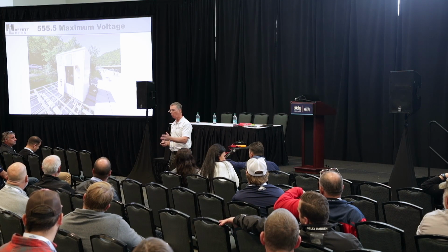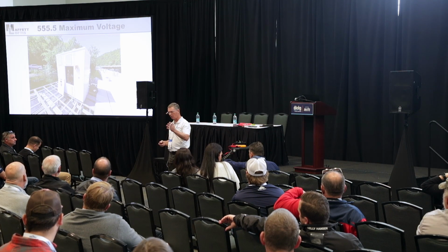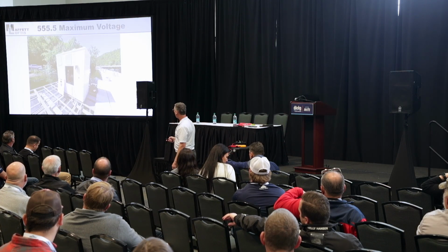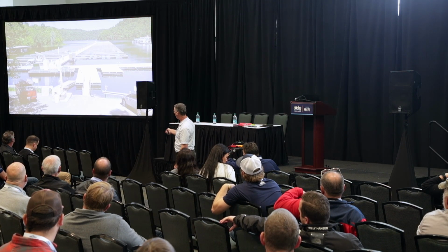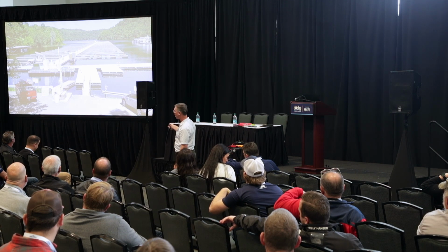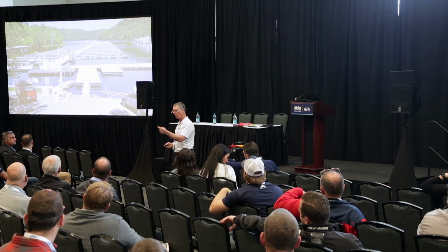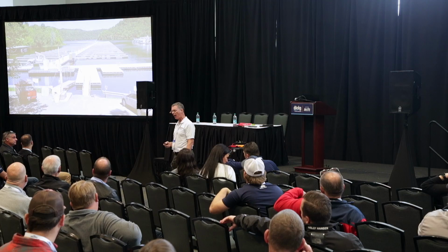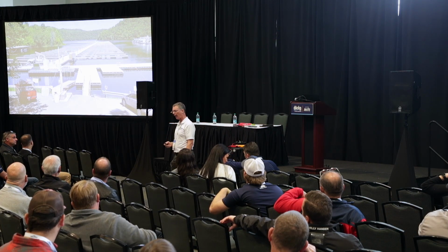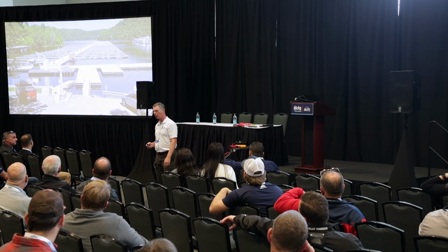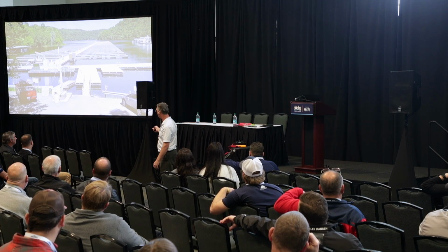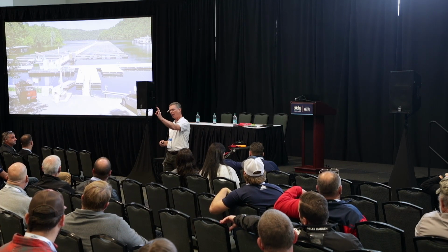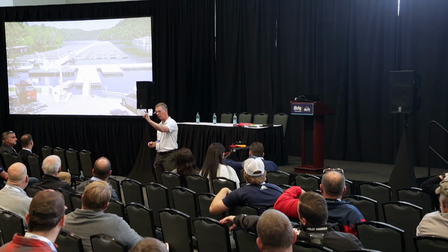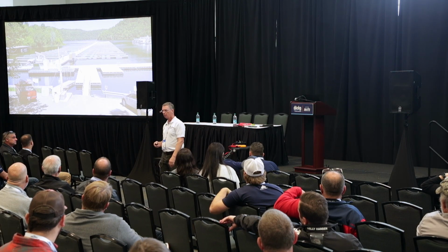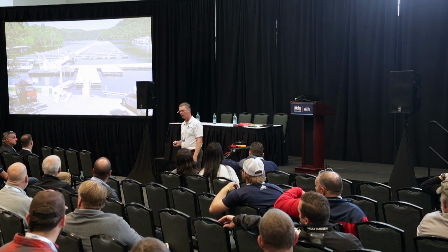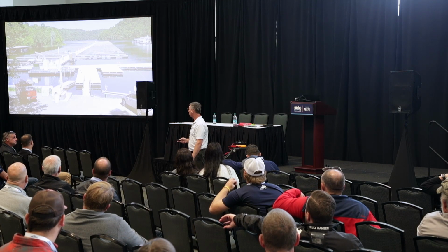But that's no matter what you do, if you've got 480 coming down. If you go back here, I've got a medium voltage one there, and I've got another medium voltage way back over there. So I don't have to carry the lower voltage all the way back, and that's where you're saving a lot of money. Think about the amount of wire you'd need through that dock structure to get all the way back over there — you're running one cable that big, or maybe 3, and if you do 3-phase... generally I do single phase. So Tom, does that answer your question, and see the benefit now? Yes, sir. Okay.